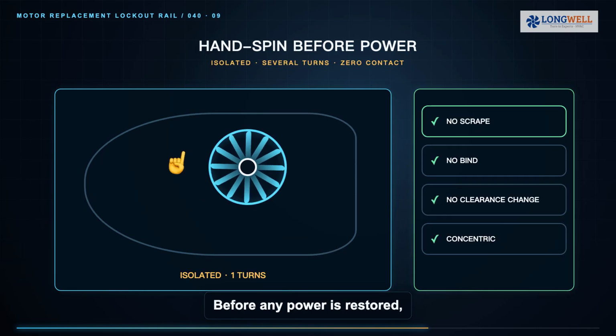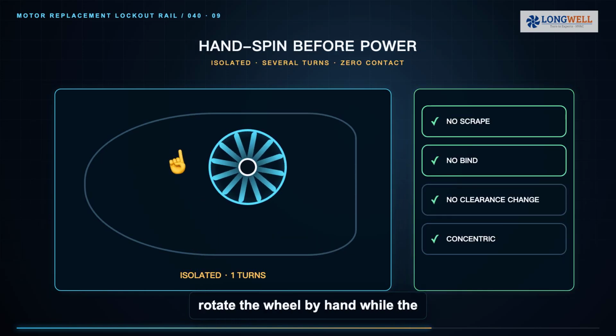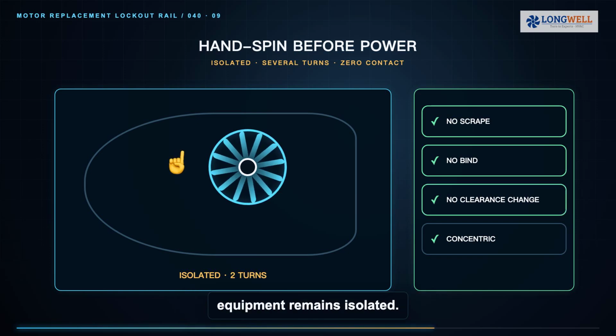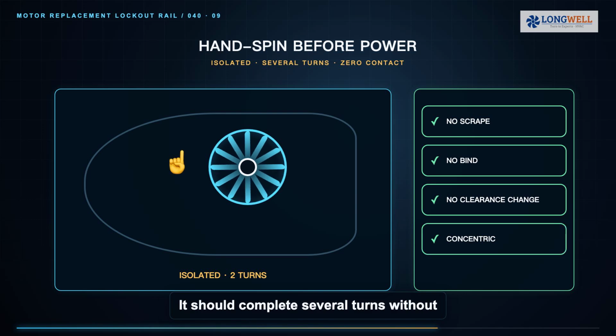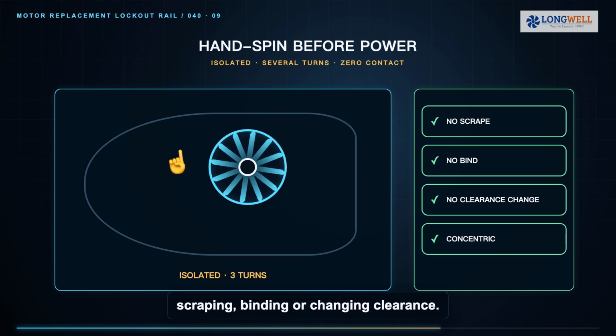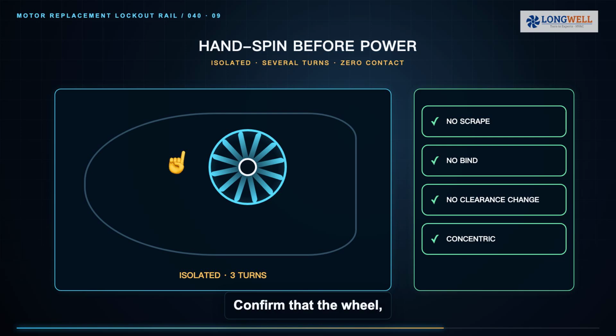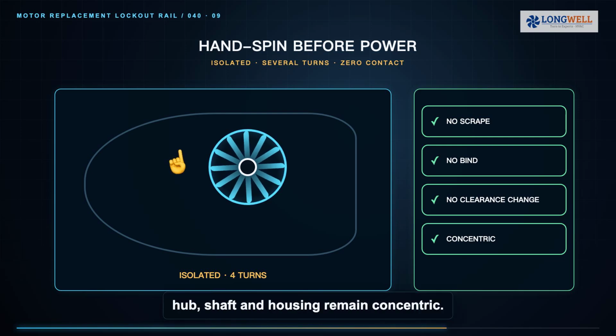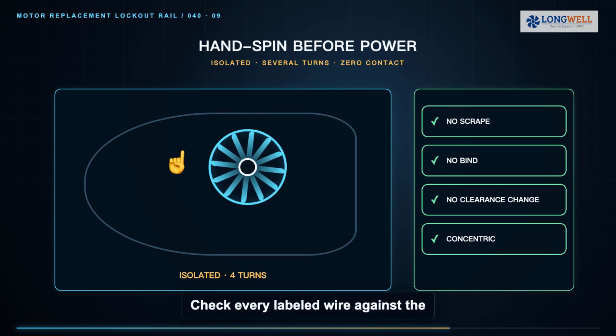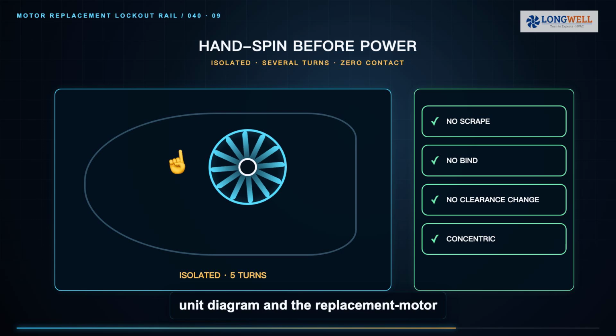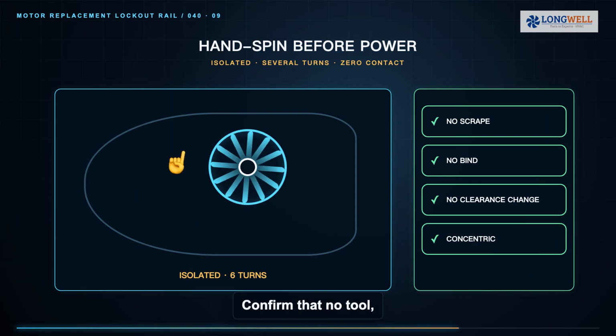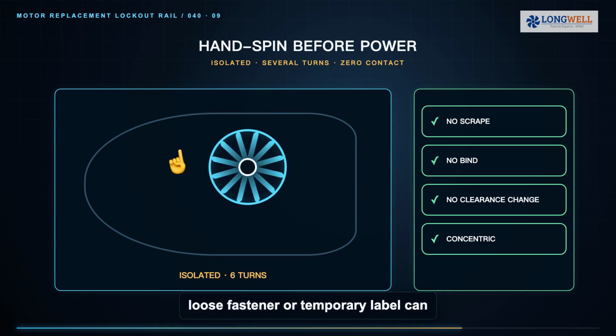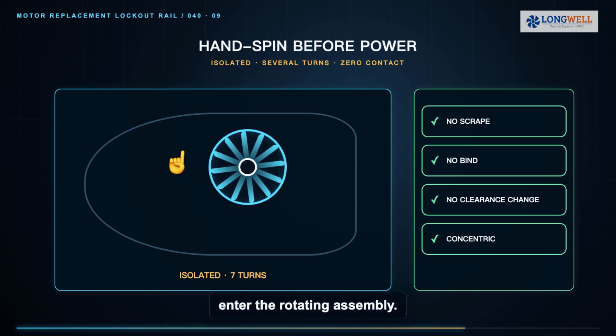Before any power is restored, rotate the wheel by hand while the equipment remains isolated. It should complete several turns without scraping, binding, or changing clearance. Confirm that the wheel, hub, shaft, and housing remain concentric. Check every labeled wire against the unit diagram and the replacement motor instructions. Confirm that no tool, loose fastener, or temporary label can enter the rotating assembly.